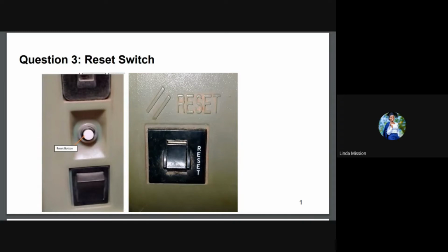And there are a number of things that you have to do in order to solve this problem. Firstly, you have to check the quality of the mains power, if it is up to standard as given by your local electricity supplier, with a digital multimeter. Then you also have to check all internal electrical connections of the concentrator to make sure that you don't have any short circuits. And also you have to check the compressor's electrical integrity. A simple test check would be to replace the compressor with a working compressor and see if the reset switch trips or not.